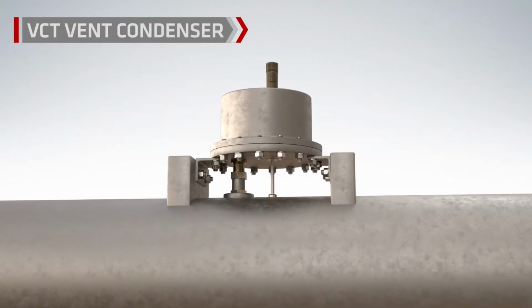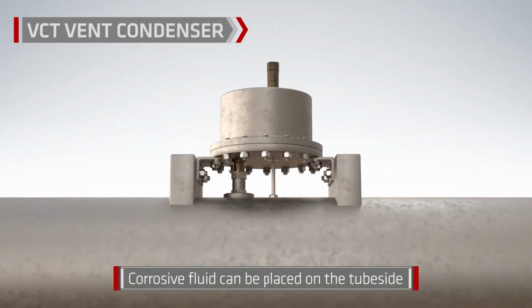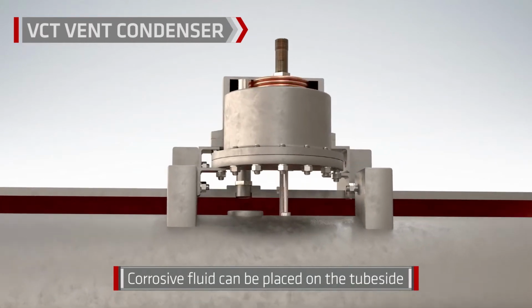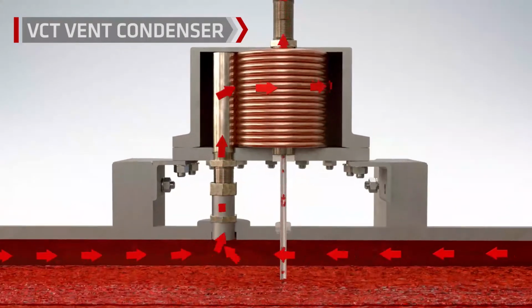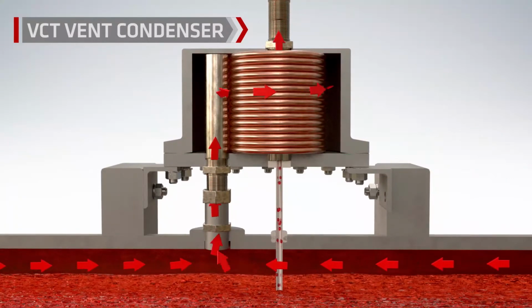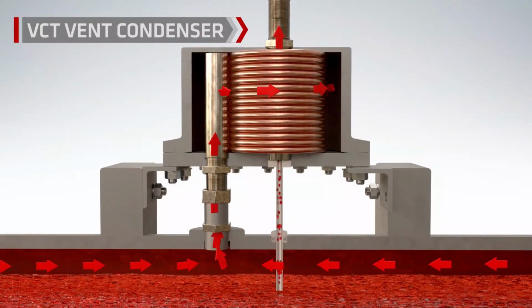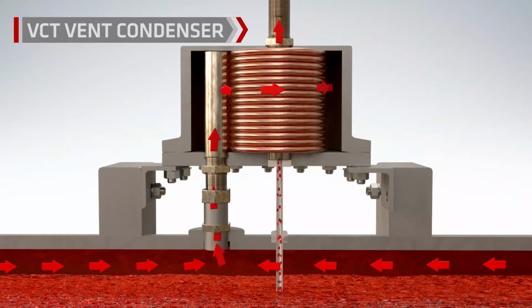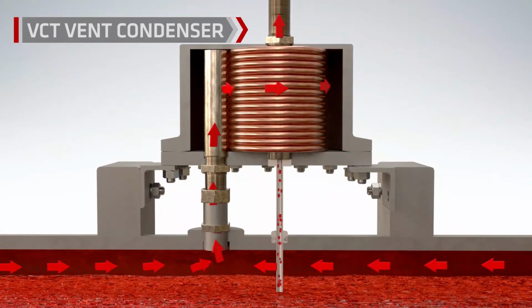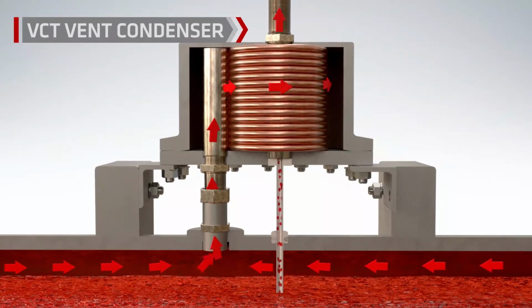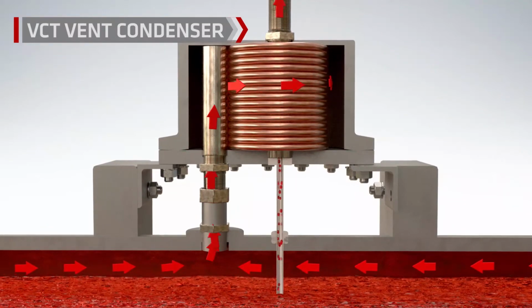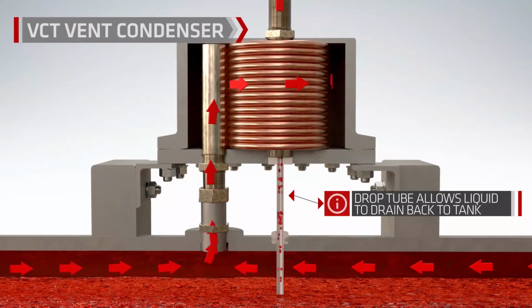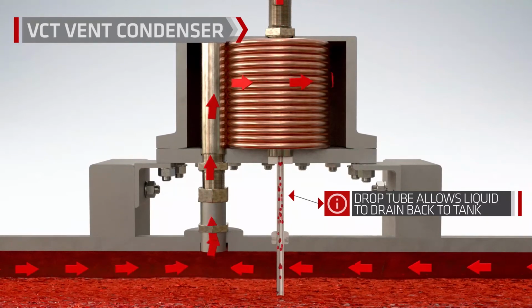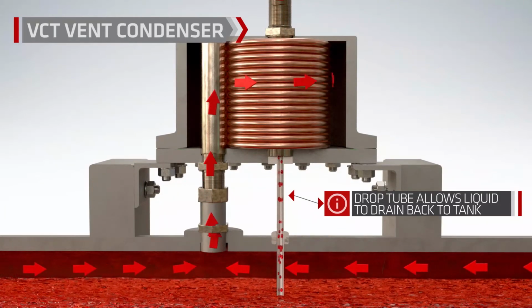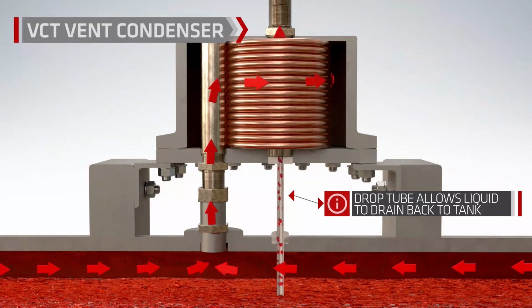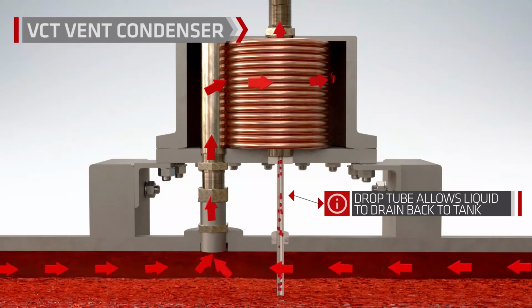VCT is used to condense the process vapor inside the tubes. This is most commonly used for corrosive fluid applications. In this design, the vapor is drawn into one manifold and is then directed through the tube coils. The non-condensable components are discharged through a connection at the top of the unit. A drain in the outlet manifold is used to pass the condensed liquid back into the tank. Tube side condensing of the process vapor also allows for subcooling of the condensate, which can be useful if the condensed fluid is needed in a chilled state for further processing.